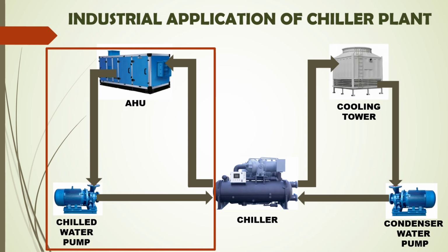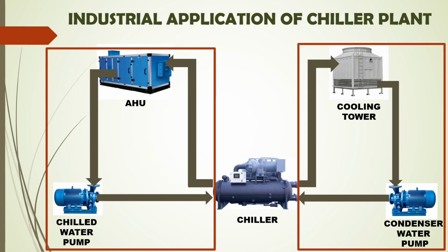In the other circuit, that is the condenser water circuit, the cooling tower and condenser water pump are connected to the condenser of the chiller. The condenser of the chiller receives hot refrigerant gas from the compressor. This heat is transferred to the condenser water, warming it up. The hot water is then pumped to the cooling tower, where it releases heat to the atmosphere and cools down. The cooled water is then pumped back to the condenser, where it absorbs heat again and the cycle continues. Inside the chiller, the refrigeration cycle continuously runs, ensuring heat transfer between the evaporator and condenser to maintain the required cooling.